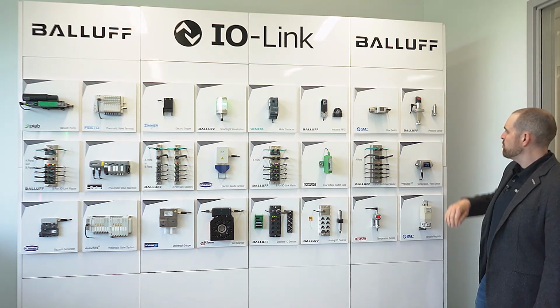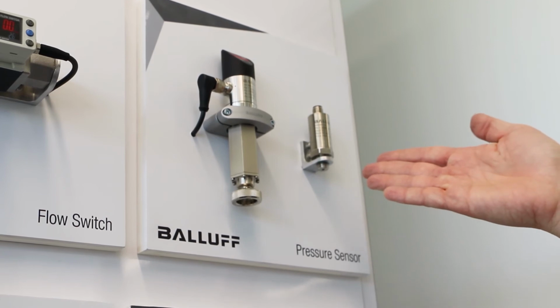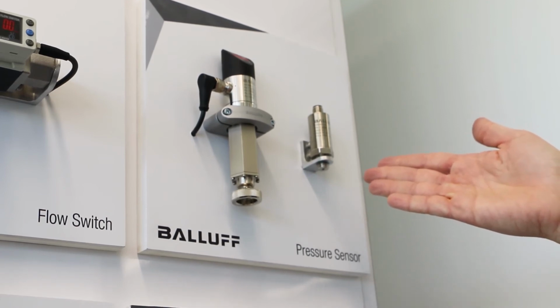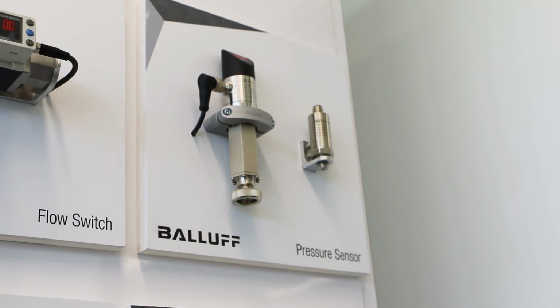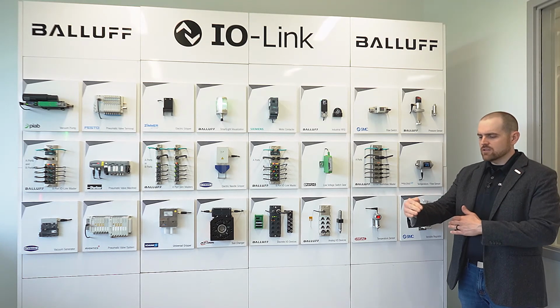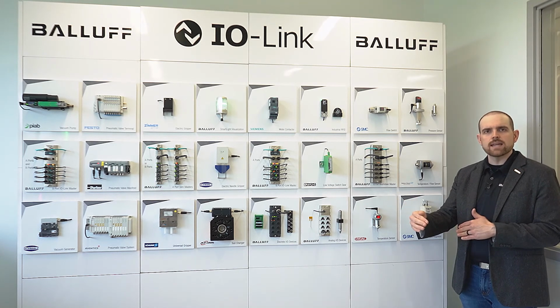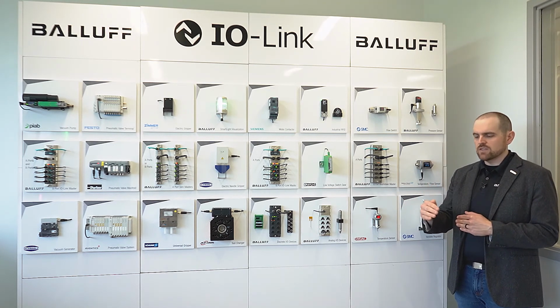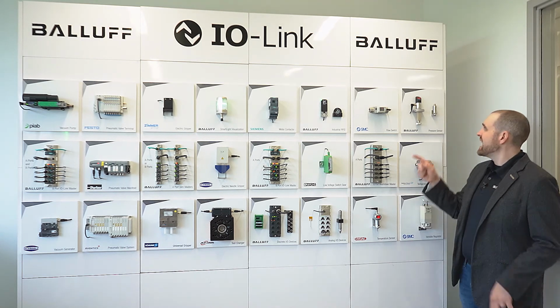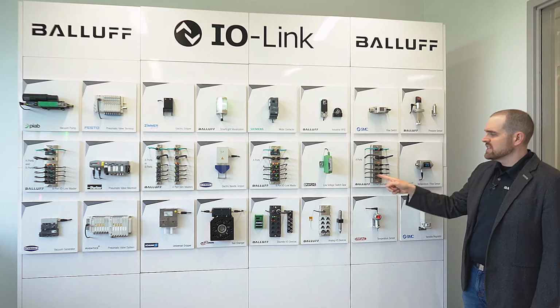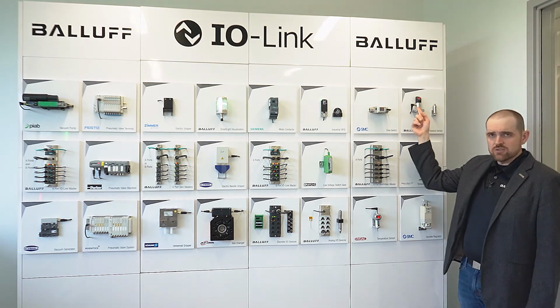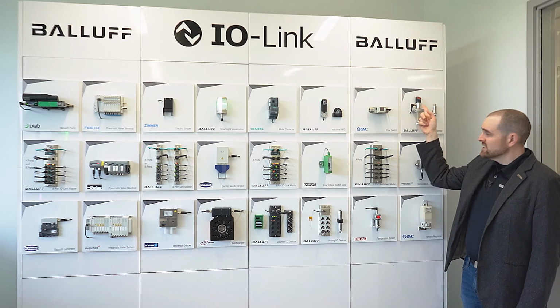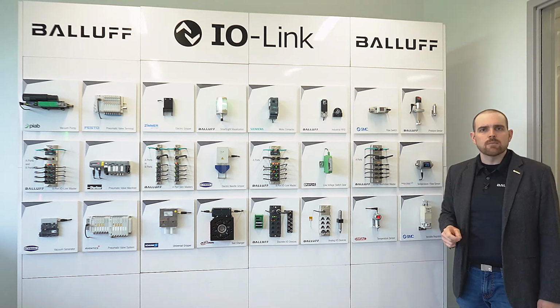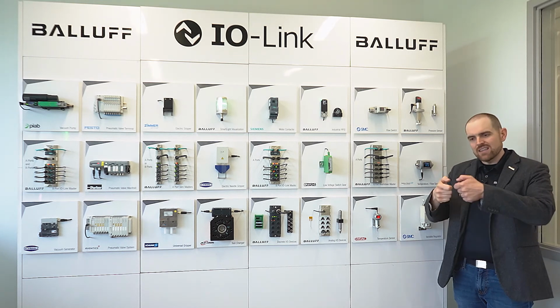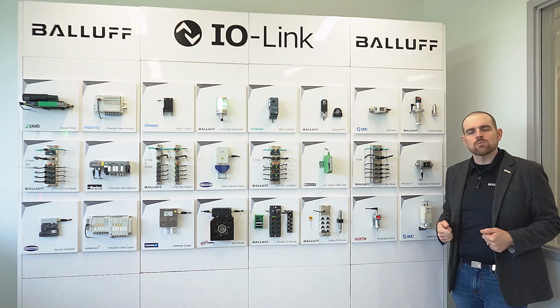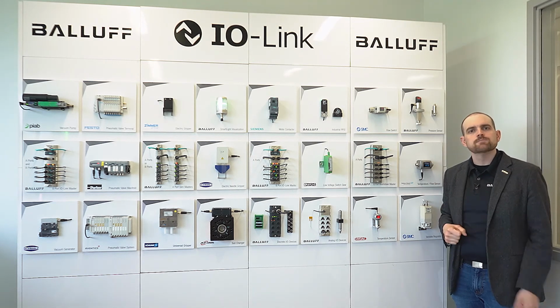And then the Balluff pressure sensor here, we have a transducer without display and a Balluff pressure sensor with display. These provide a pressure value, with set points and hysteresis control. There's tons of values inside, over 16 parameters you can set and program for the pressure sensor. What's amazing about IOLink is I can have all those settings from that sensor downloaded and stored in the master. So if something happens to that pressure sensor, it gets damaged or needs to be replaced, when I swap it out, I can automatically send the last set of parameters to the device. I don't have to sit there and set 16 settings with a two-button push button, which can be frustrating.